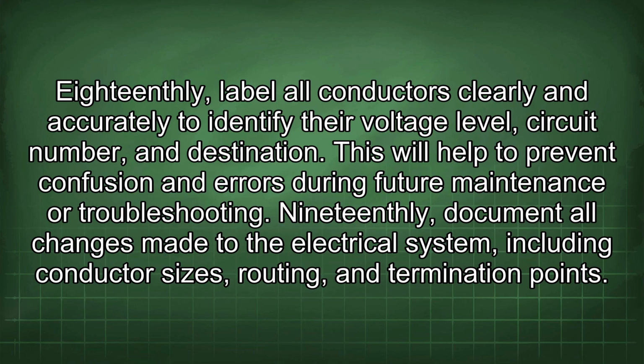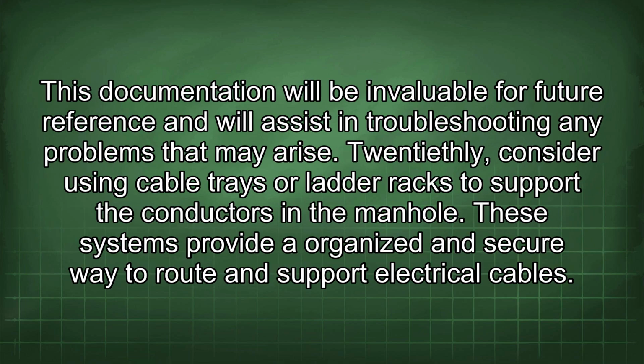18thly, label all conductors clearly and accurately to identify their voltage level, circuit number, and destination. This will help to prevent confusion and errors during future maintenance or troubleshooting. 19thly, document all changes made to the electrical system, including conductor sizes, routing, and termination points. This documentation will be invaluable for future reference and will assist in troubleshooting any problems that may arise.